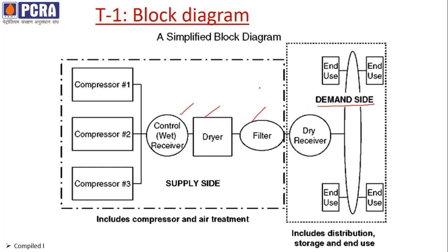The second tool is the pressure profile. If you see the compressed air, if this is the compressor outlet, 110 psi, it is almost 7 bar. If you create a pressure profile in any industry, it will be like this. After the dryer and filter, those pressure drops will be there. So from 110, it comes to 90 at the discharge of the filter.